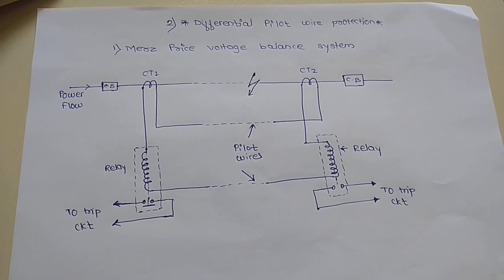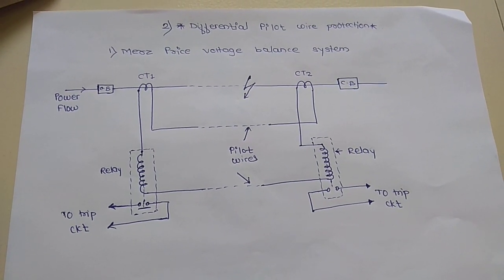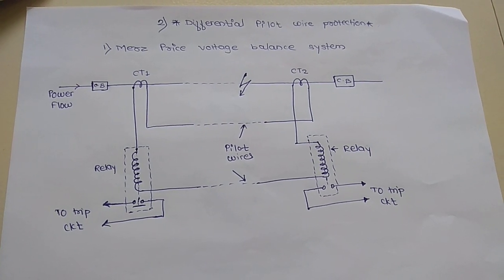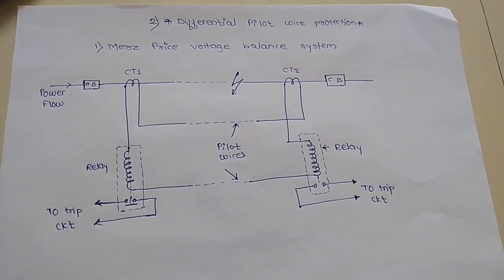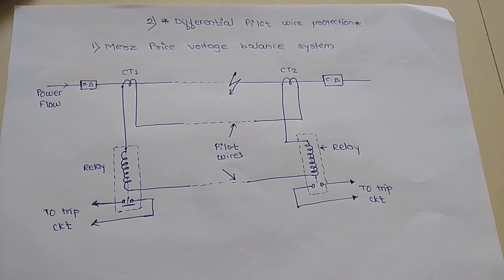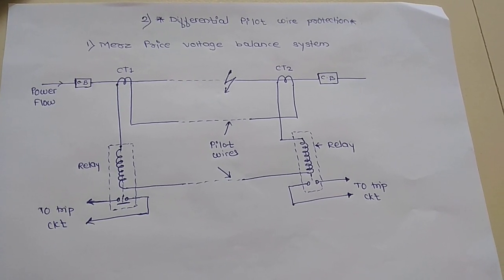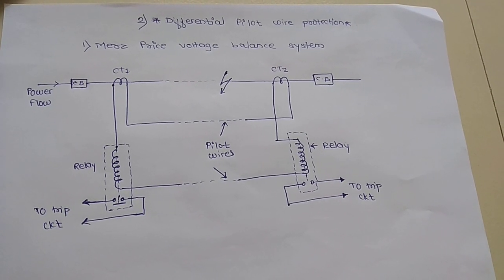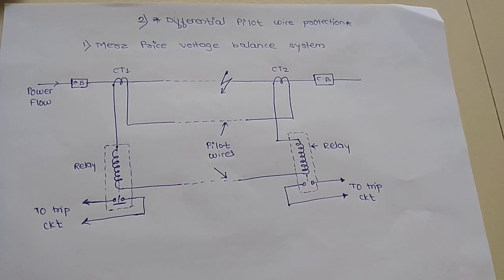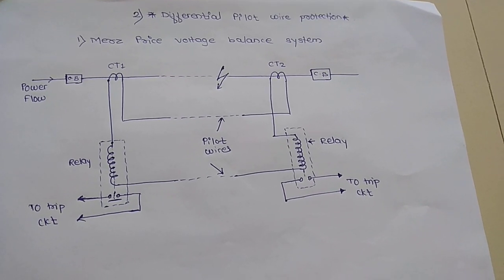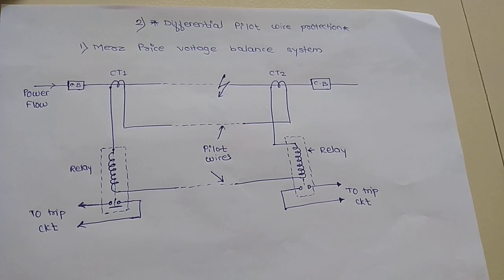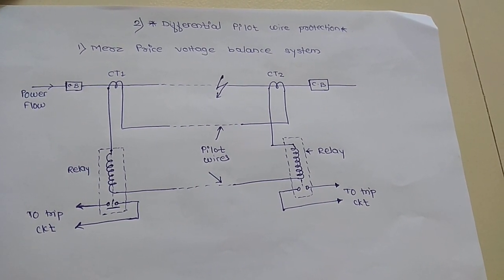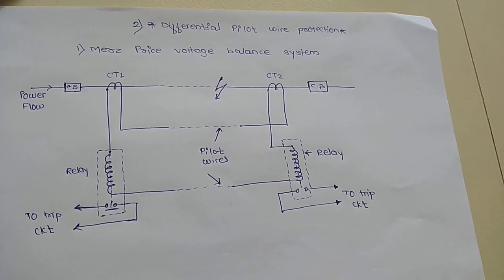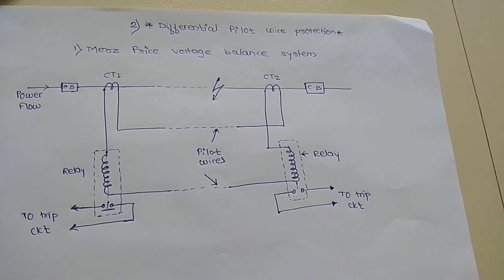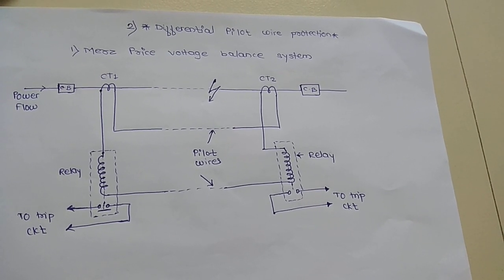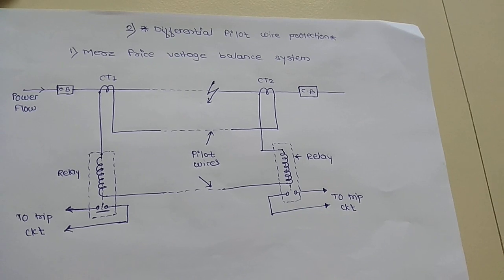Differential pilot wire protection is based on the principle that under normal condition, current entering one end of the line is equal to current leaving at the other end, so the relay will not operate. As soon as a fault occurs, this condition no longer holds, the incoming and outgoing currents are not equal, and the difference of current flows through the relay, giving a trip command to the circuit breaker.